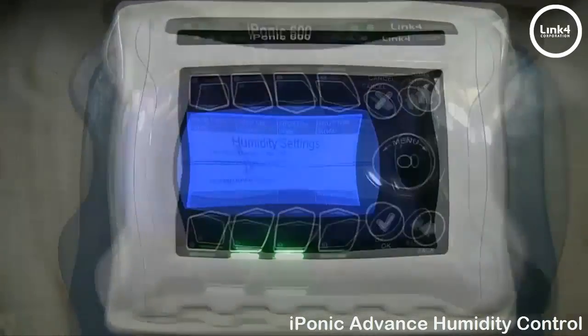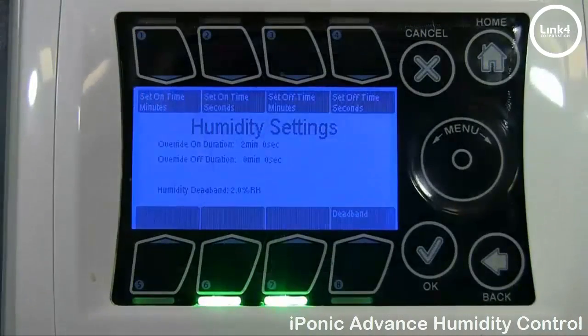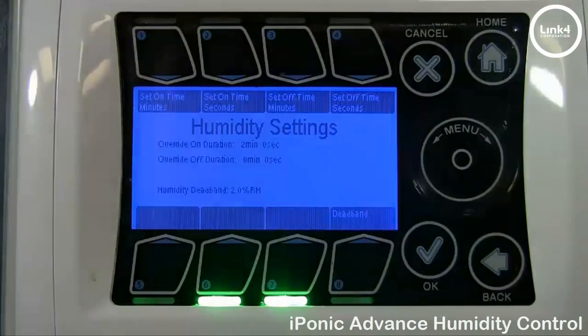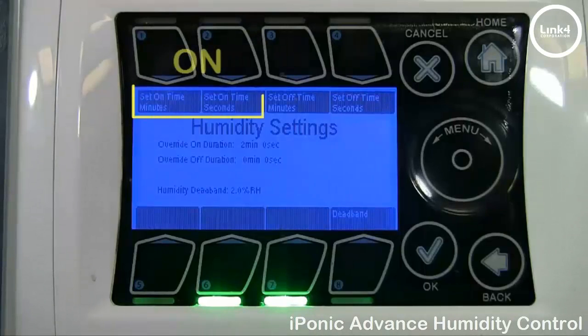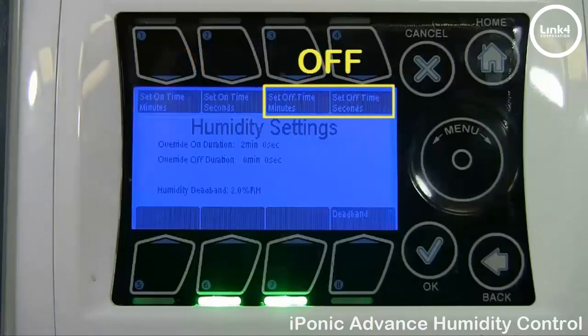humidity settings. Unlike temp staging, where equipment turns on and just stays on while in a cooling or heating stage, relative humidity staging gives you a cycle option where you can gradually increase humidity and dehumidity till set point thresholds are met plus the deadband. Button number 1 and 2 are for the on time, minutes and seconds, and button number 3 and 4 are for the off time in minutes and seconds.